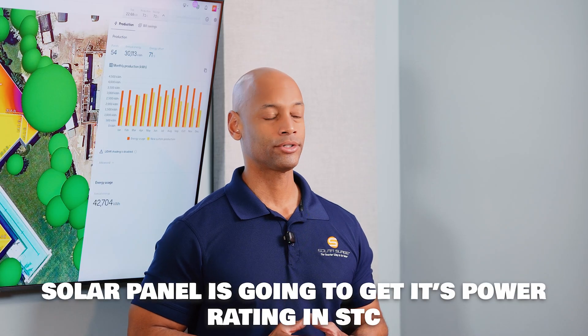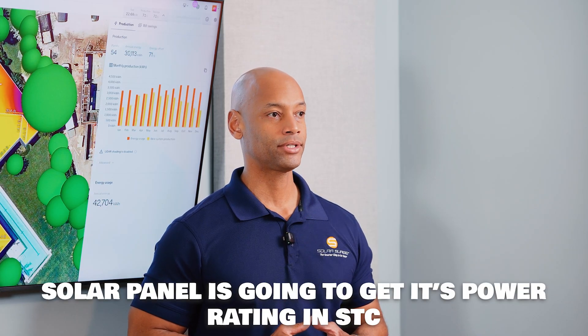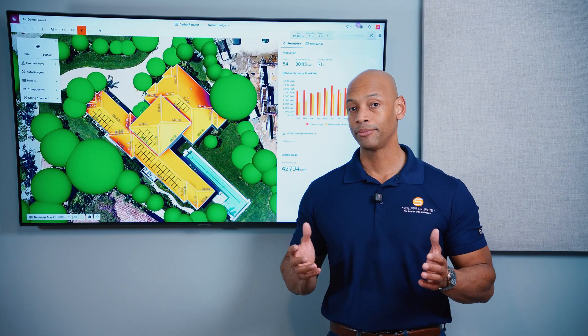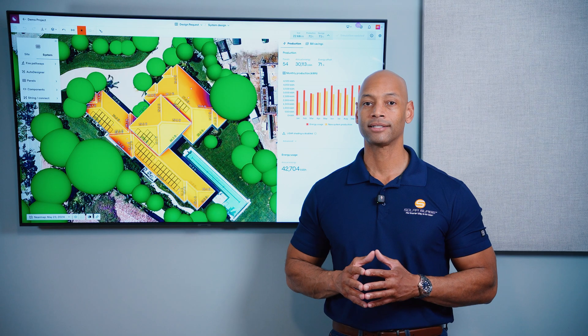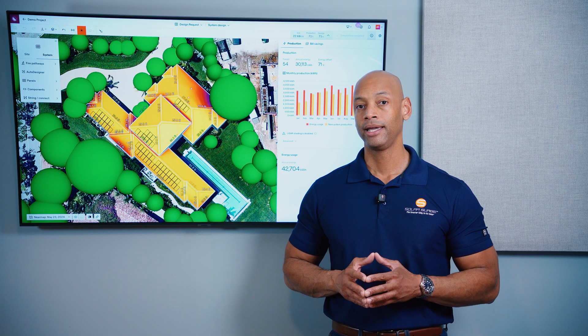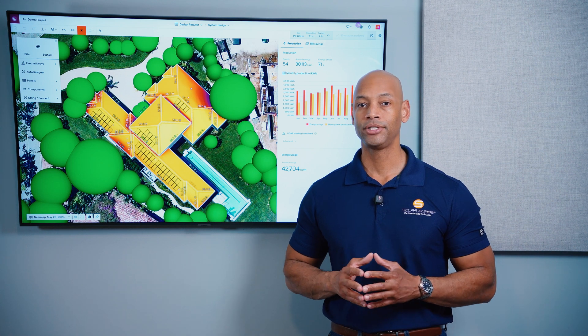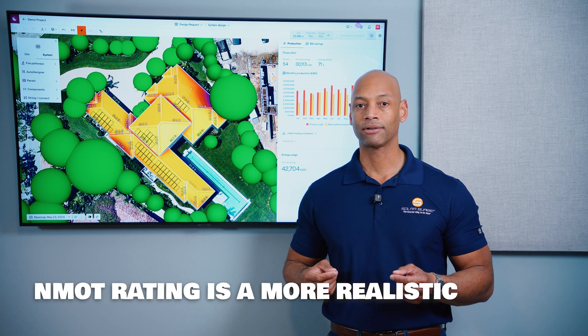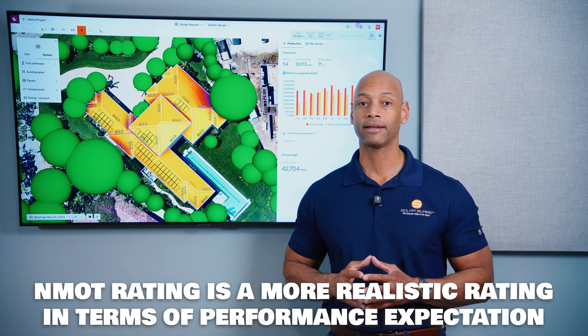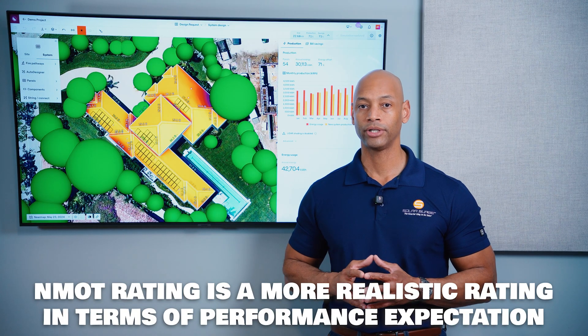Realistically, in the real world solar panels are not going to be operating in those conditions. The sunlight is not always going to be hitting the solar cells perpendicularly as the sun moves throughout the sky during the course of the day — the sunlight will be hitting the solar panel at a slight angle. You may also have partly cloudy conditions, so you're not getting that full intense direct sunlight all of the time. That's why the NMOT rating on a solar panel is a more accurate representation of what you can expect under real-world conditions.